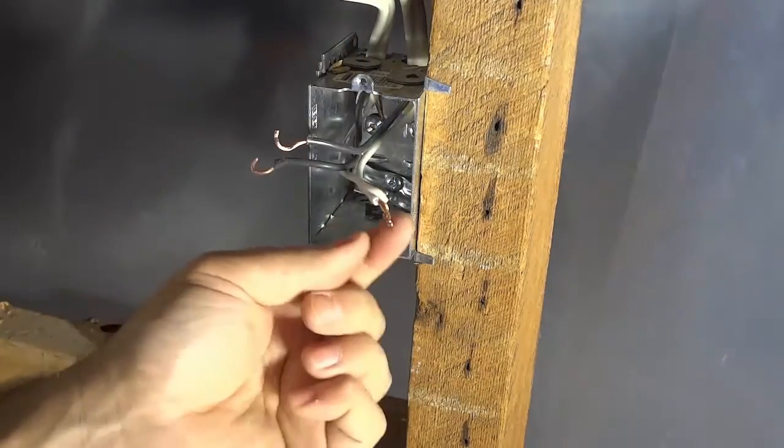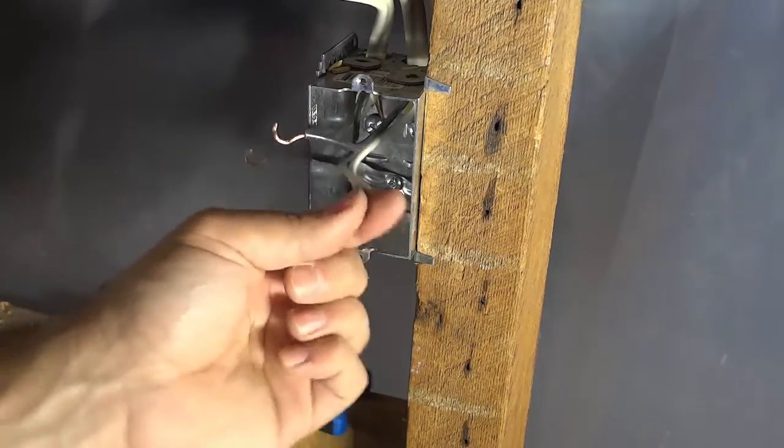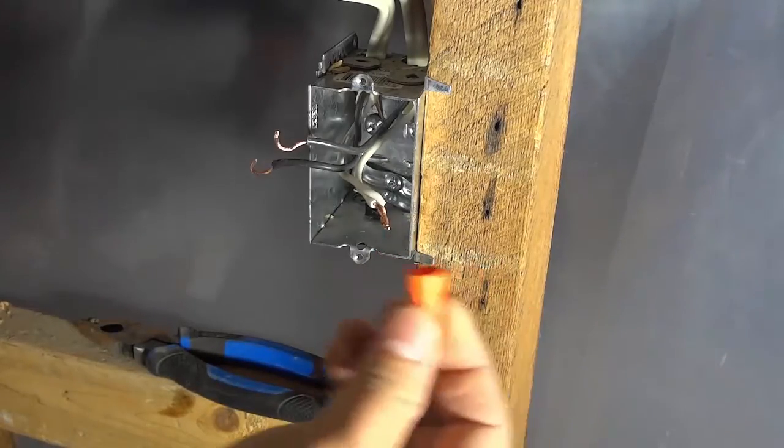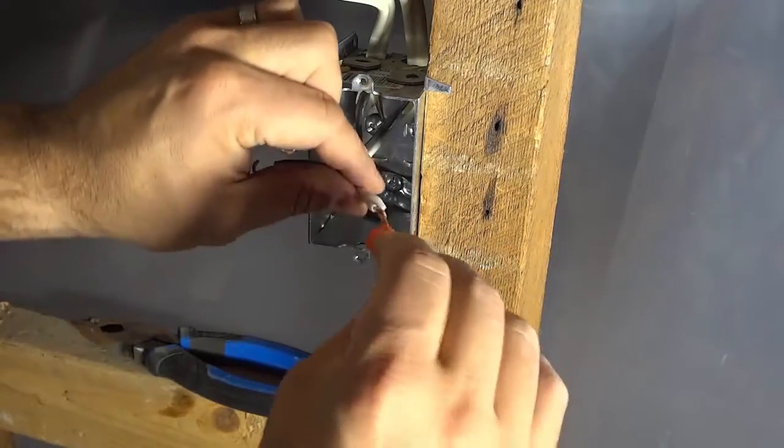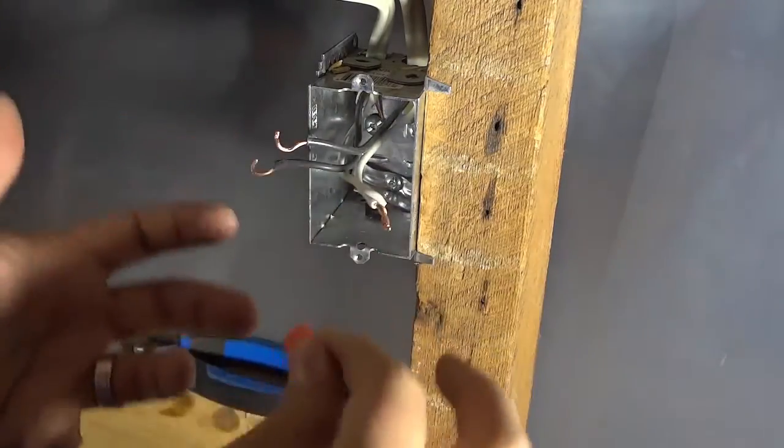Now I did forget to mention that when I was twisting these, I was twisting them together clockwise. So you twist these together clockwise and then you get the wire nut or the marrette, and you twist it onto those two twisted wires clockwise. That really just double tightens them and makes sure nothing is going to come loose.